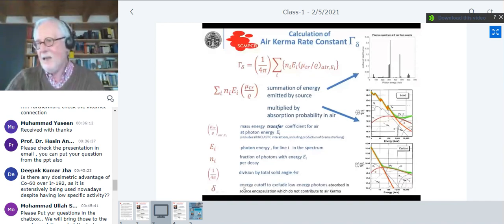And what we also do for technical reasons here is we have an energy cutoff. That is, we exclude low energy photons, lower than something like 5 or 10 keV. These are photons which normally don't reach the patient, which are also not included in the air kerma rate that we would measure, because they are already absorbed in the encapsulation of the source, so they don't contribute. So this gives us this equation up here.